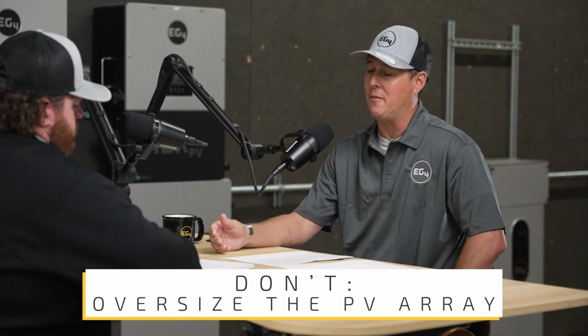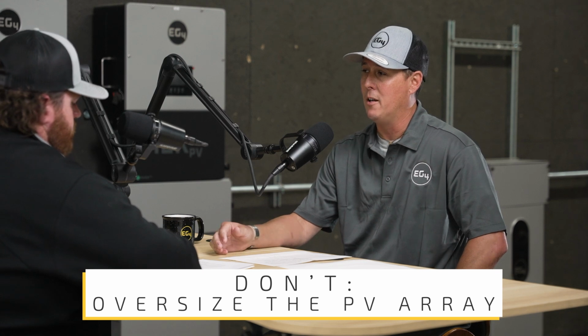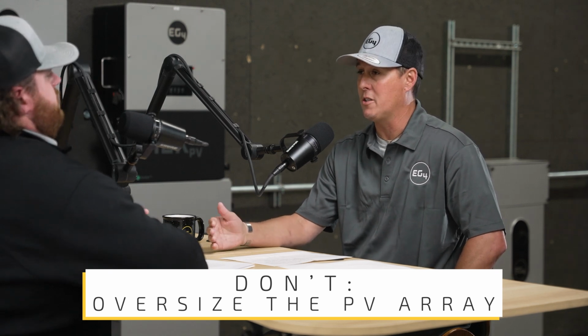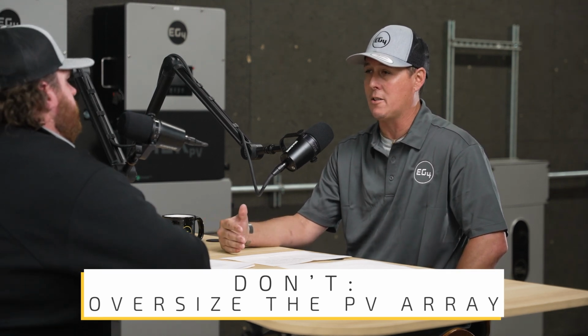This goes back to what we were talking about earlier. Don't oversize the PV array. This is a big one. I've had multiple customers that have built DC strings to, let's say, 550 volts DC, and our bus bar internally is rated to 600 volts. 550 is fine until you get that cold weather drop. Every time winter hits, this happens. So you get guys that build systems to 550 volts, they have one solid cold snap - you guys had Snowmageddon out here in Texas a number of years ago - that would have had a dramatic increase in your DC voltage.